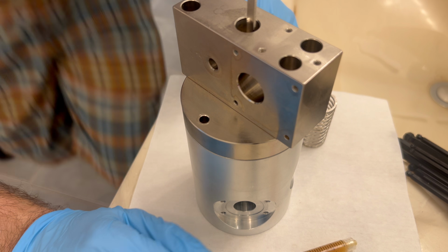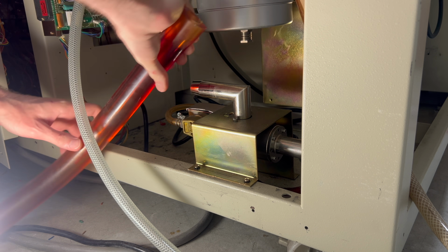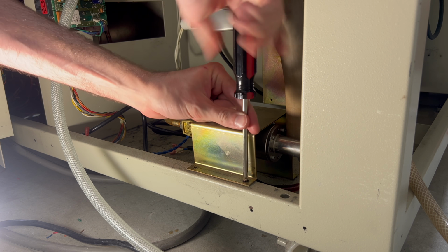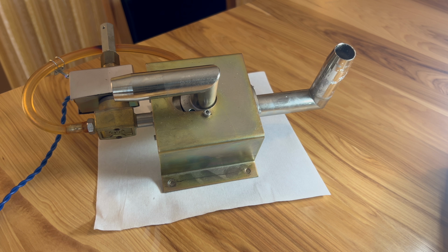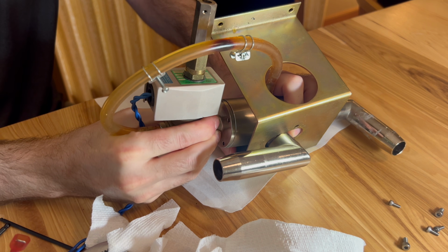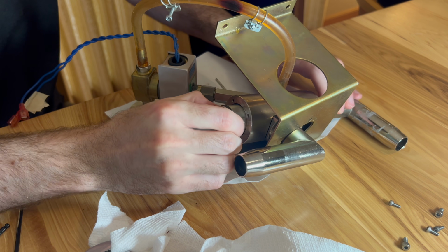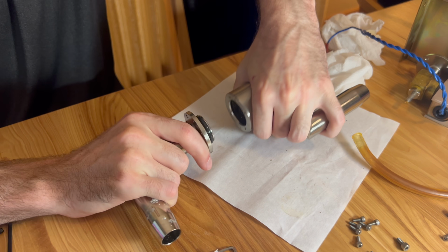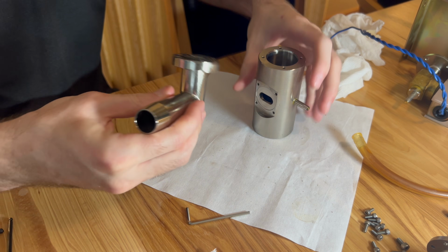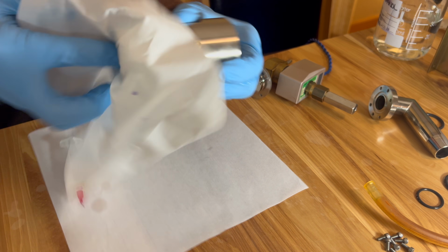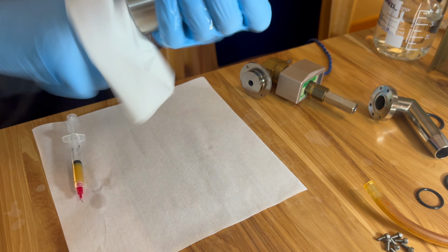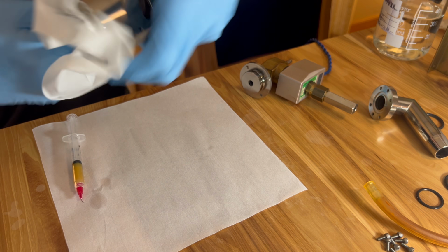Thanks, Martin. Since the vacuum system is apart already, I'm also going to recondition the RP vent valve. This small valve on the bottom is a protection valve that isolates the entire SEM from the roughing pump. This protects the diffusion pump from atmospheric pressure in case a power outage or other failure causes the rotary pump to stop working. Same as before, I cleaned it with acetone and isopropanol and lubed it with Apiezon L grease.